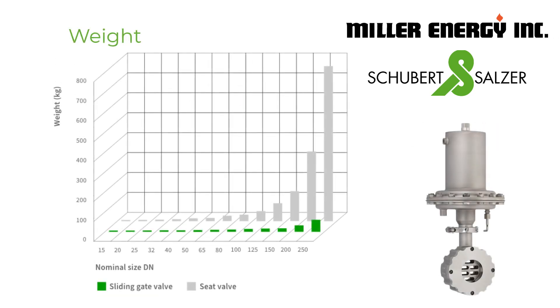The low actuating force and short stroke allow the use of smaller actuators. Combined with the space-saving construction, weight and installation dimensions are minimized, particularly in mid to large nominal sizes. For example, a six-inch globe valve weighs approximately 330 pounds, whereas a sliding gate valve of the same nominal size weighs a mere 33 pounds.